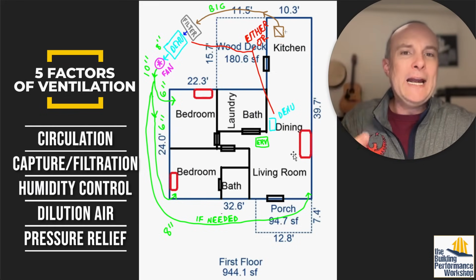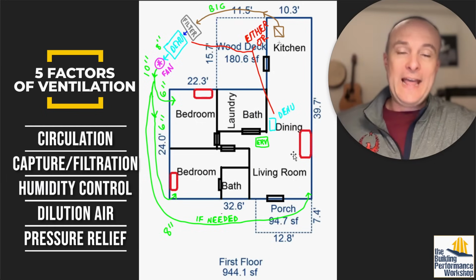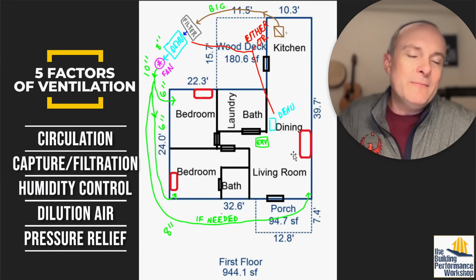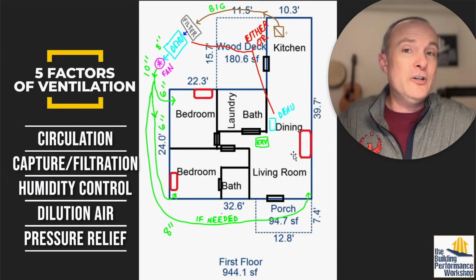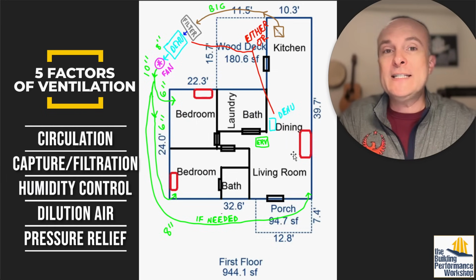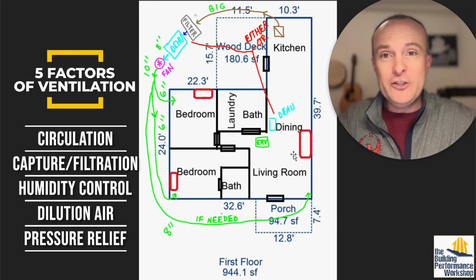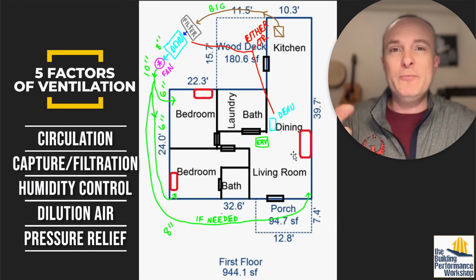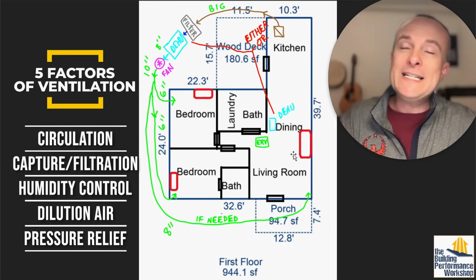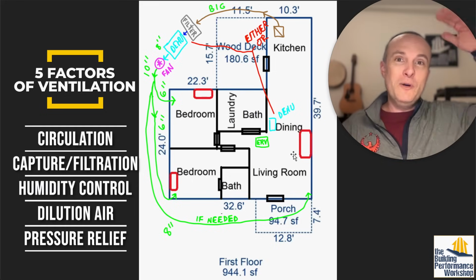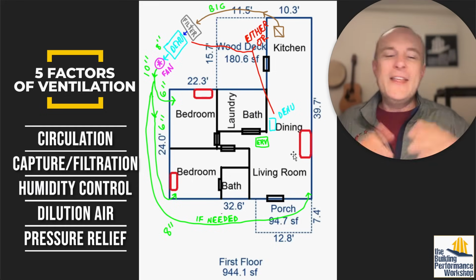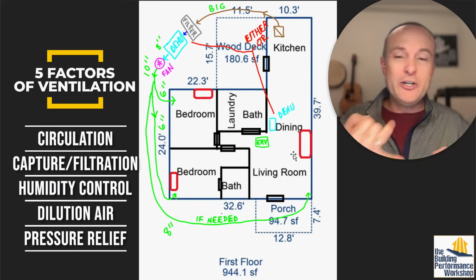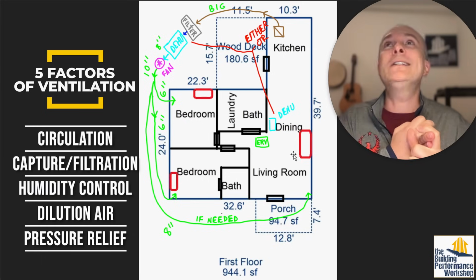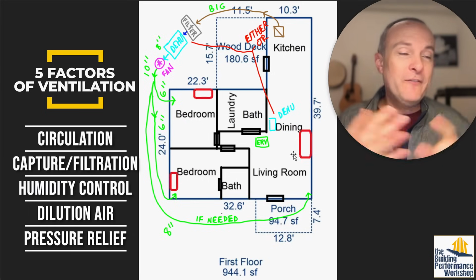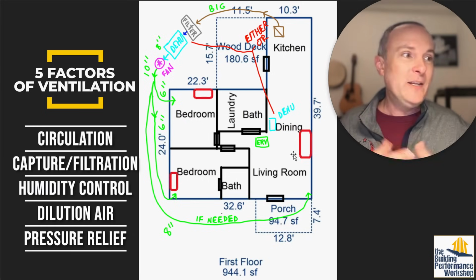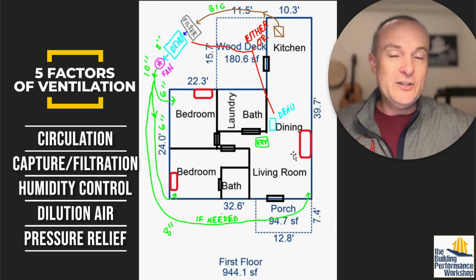Then we want to pull air out of the other end of the house. I normally wouldn't recommend putting a return in a kitchen, but since this system's purpose is just filtration, we use the Aprilaire 2516 filter—the one I always recommend, 31 by 28 inches, basically the biggest filter you can get. That lowers your static pressure and means only a once-a-year filter replacement. The filter itself costs about $150, so that's as little maintenance as you could possibly get.